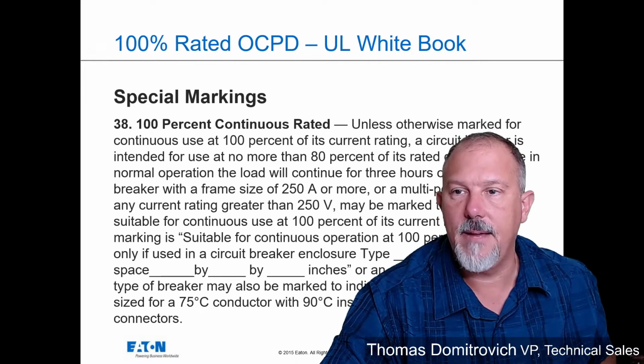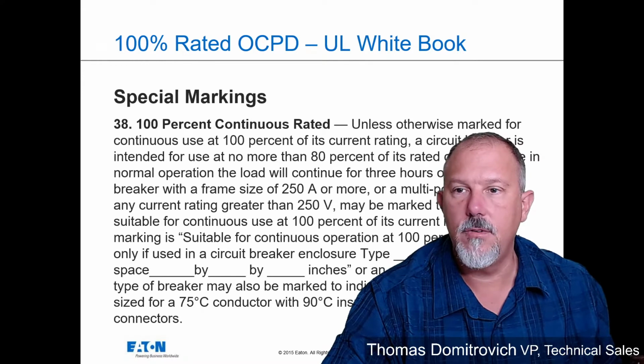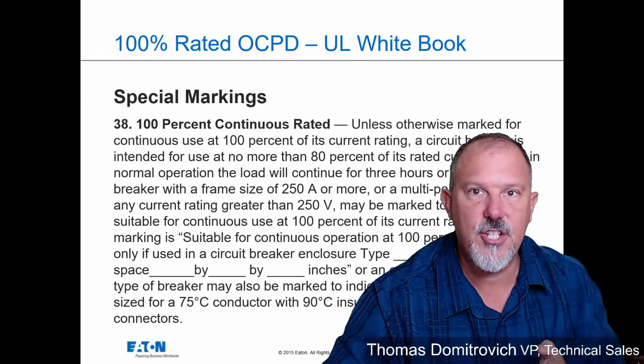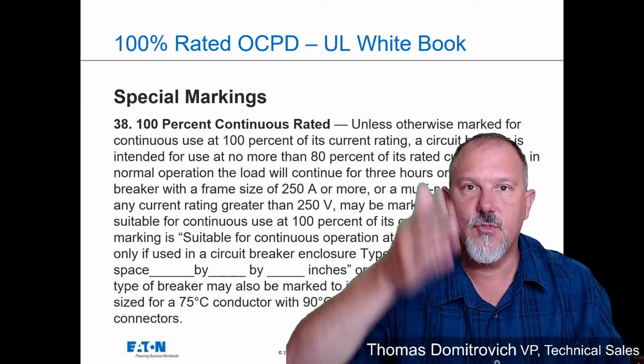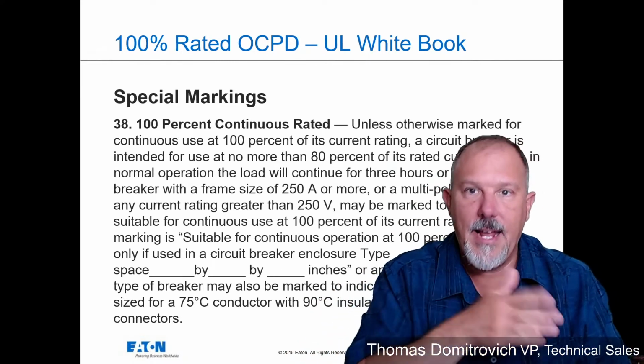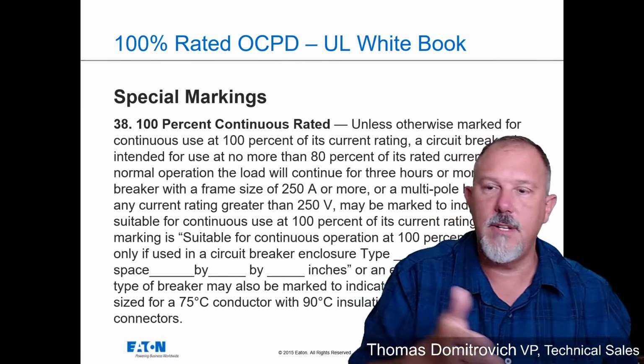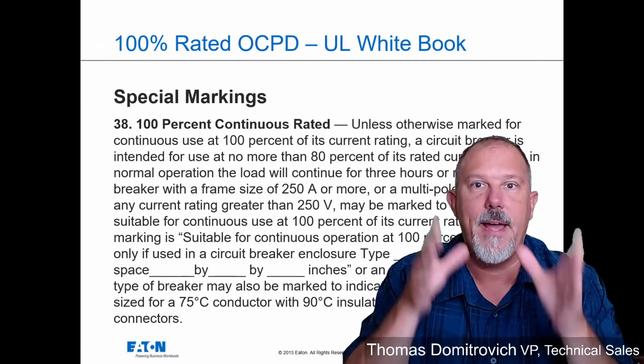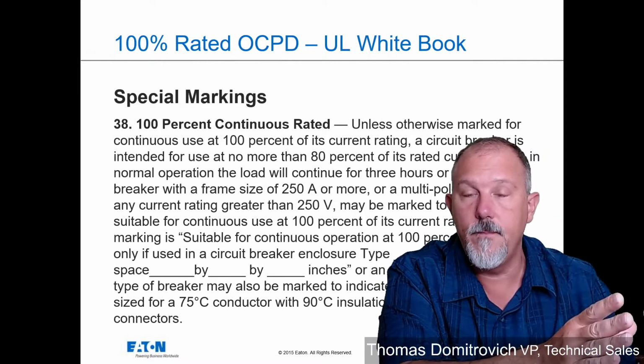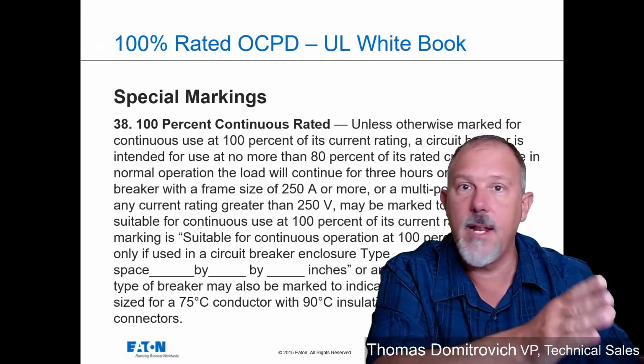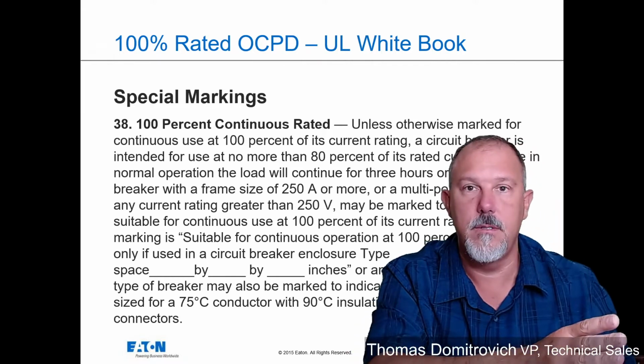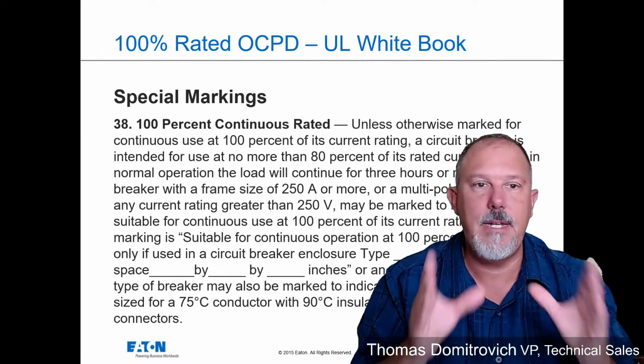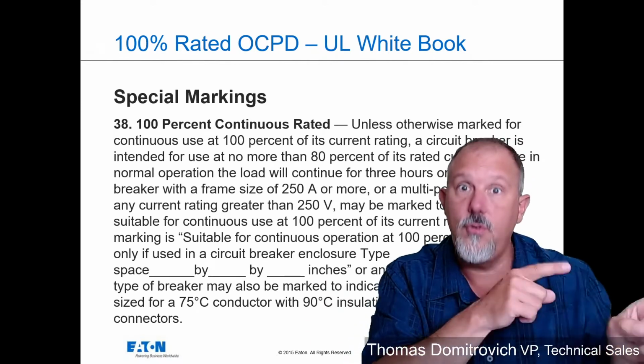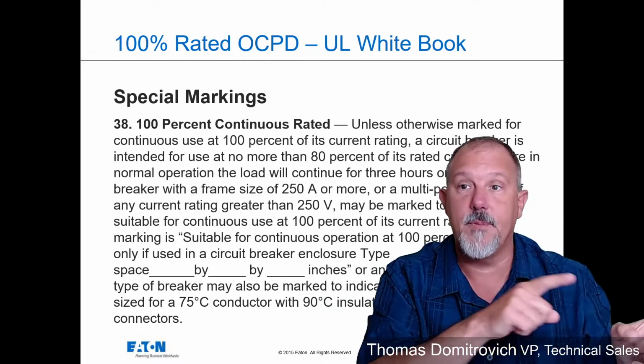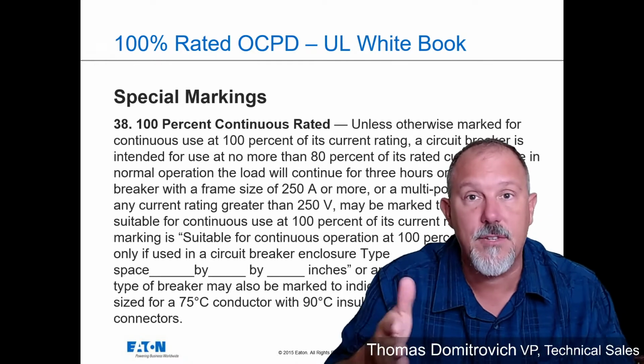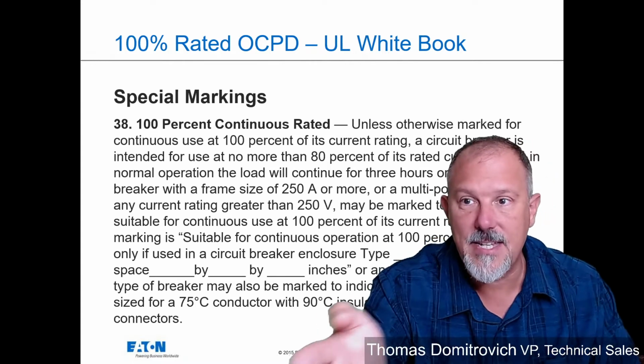If I buy a 2000 amp frame, 80% breaker, and turn the long time down to 1600 amps, so that's your 80%. A circuit breaker is rated to carry 80% of its rated current. So if I take that 2000 amp breaker and turn it down to 1600, which is 80%, I can use a conductor, 1600 amps worth of conductor can carry 1600 amps. I'm perfectly fine. I don't need 100% rated on anything. I can use that conductor at 1600 amps because this breaker can carry 80% of 2000 amps, and I've set the setting for that.